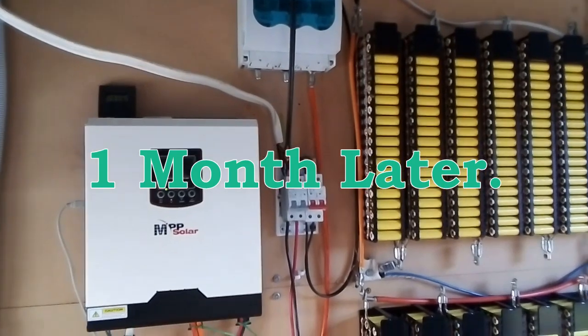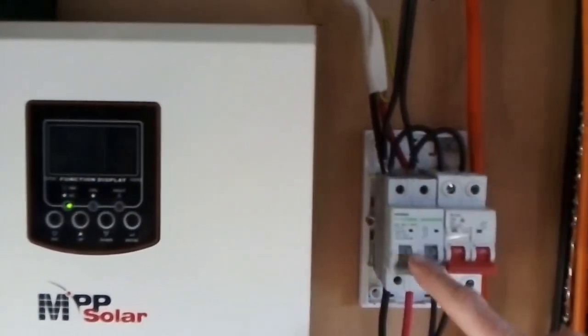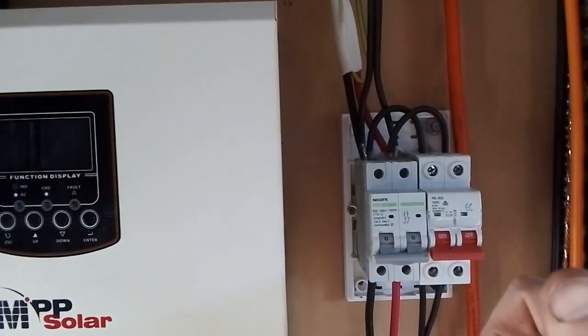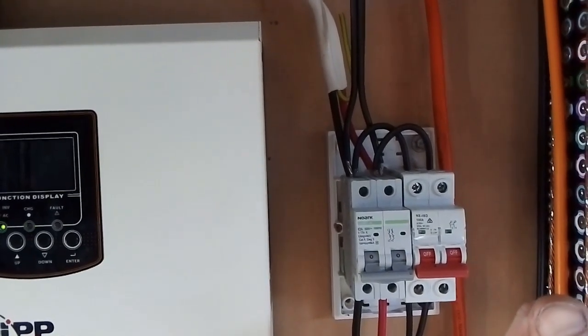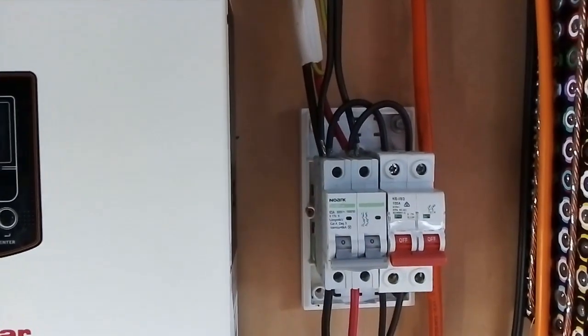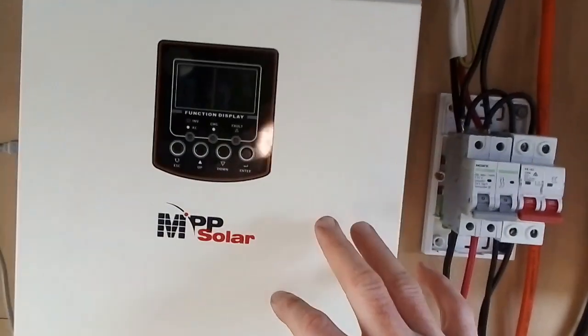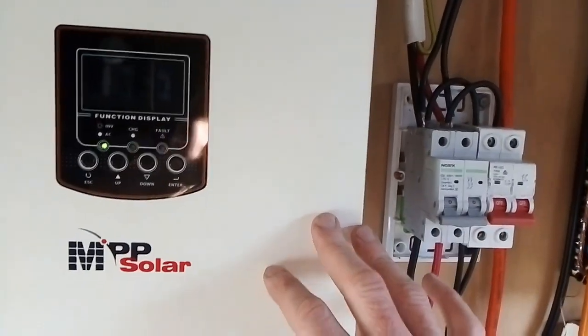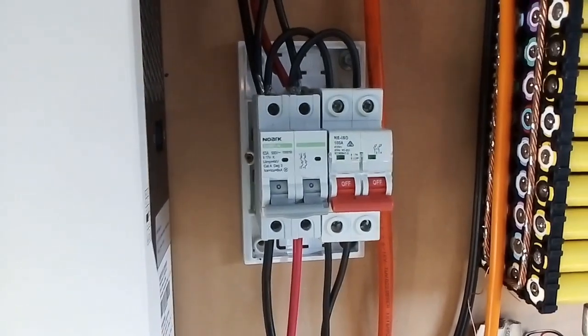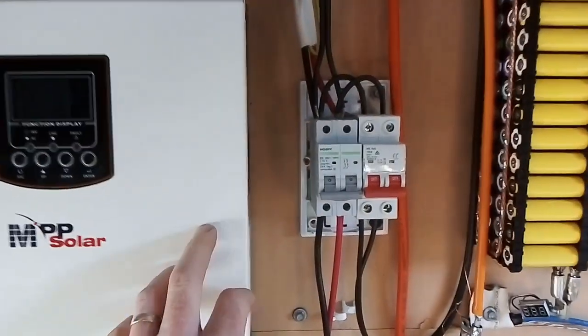To summarize: I've been adding extra panels when I shouldn't have. I've had it running through this switch, coming in straight and still going through the breaker. The breaker is 63 amps, and with the shed panels plus roof panels — another four times 5.25 amps — that could have equalled about 75 amps all up. So yes, it's tripped quite a few times. The inverter doesn't want to see more than 50 amps, but it's still working fine — it's doing its job by cutting out when it's over-amped. I'll be fixing it and keeping within the manual's 50 amp limit.